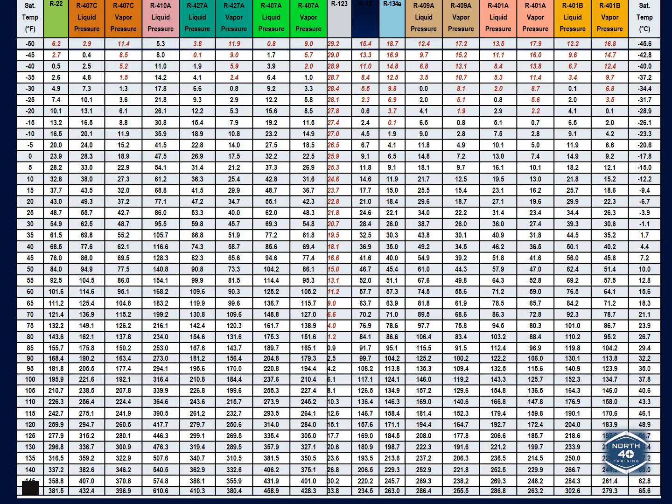Those digital gauges are figuring out the superheat and the subcooling for you, but what they're doing is they've got this PT chart pre-programmed in, which is extremely handy, but it also occasionally dumbs us down a little bit. We forget about the math and the process that goes into the backside of learning those things. So it's very important to understand how the pressure-temperature relationship goes together, and then also how to manually take a pressure and make it correspond to a temperature with a particular refrigerant.